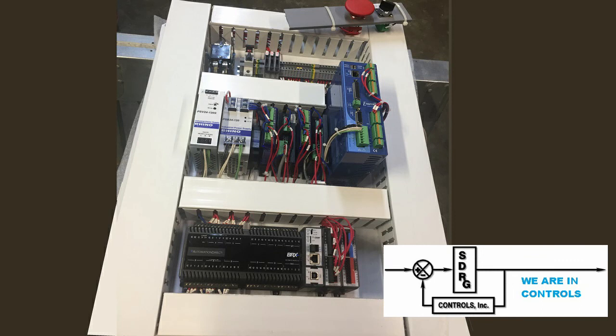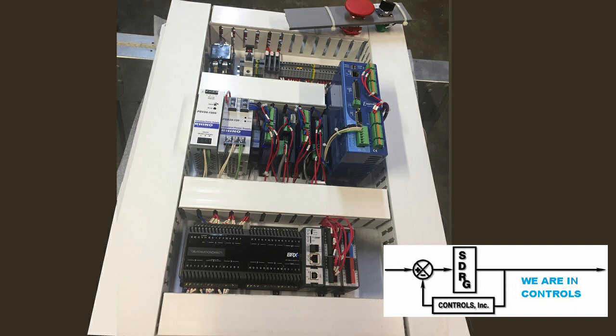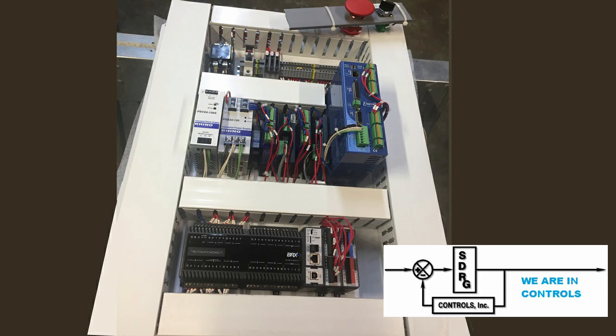This panel also included breakers, fuses, power supplies, terminals etc., which made up the complete control system. During testing, this panel was wired to the various devices discussed previously, with external processes using simulated signals, such as time-delayed relay feedback. This testing was with a small part of the overall system equipment, but it was an important verification of the core processing which ensured the high-speed functionality of the system.